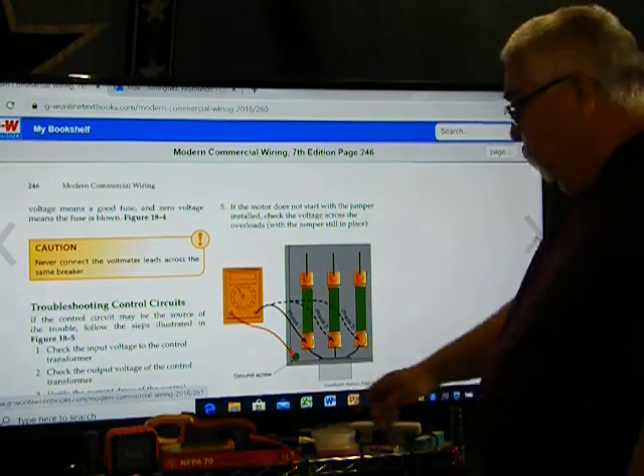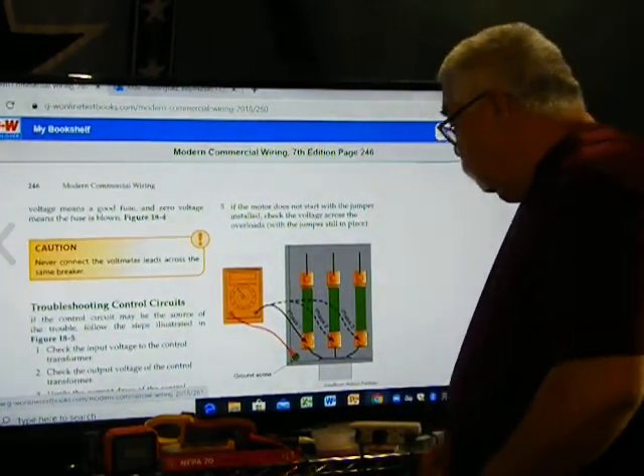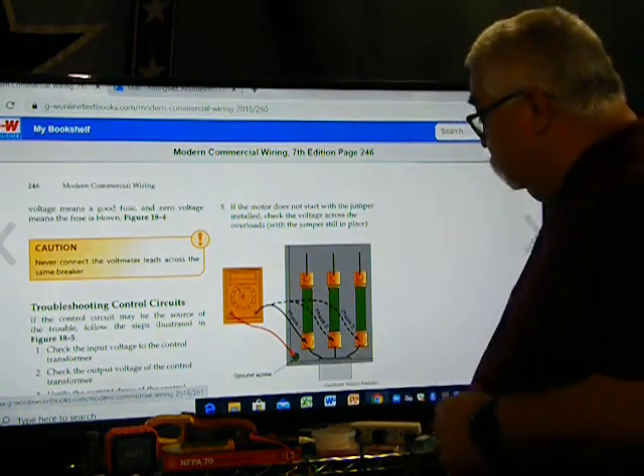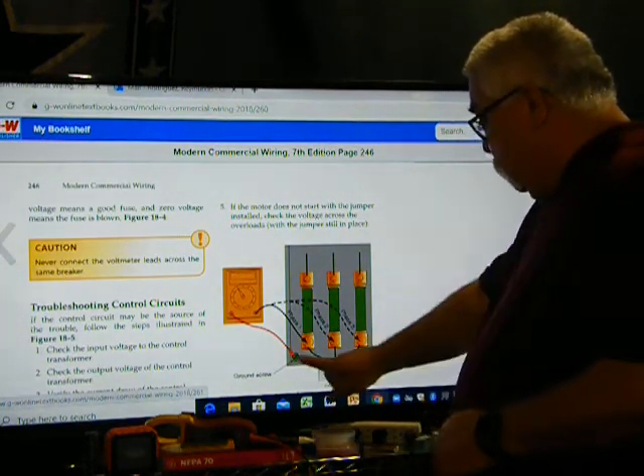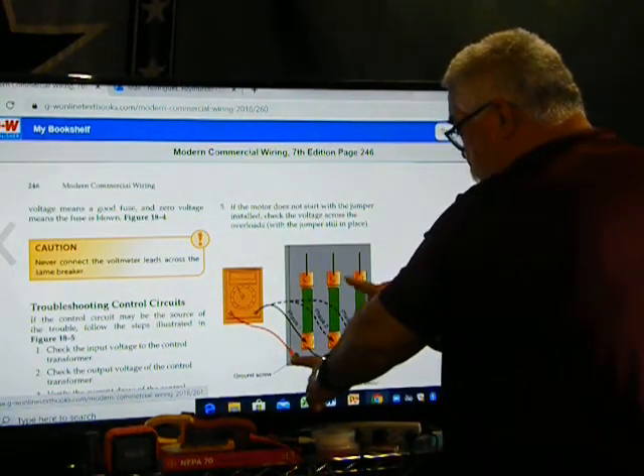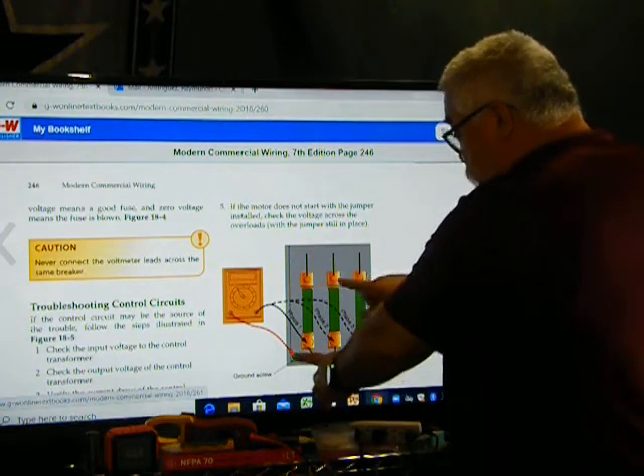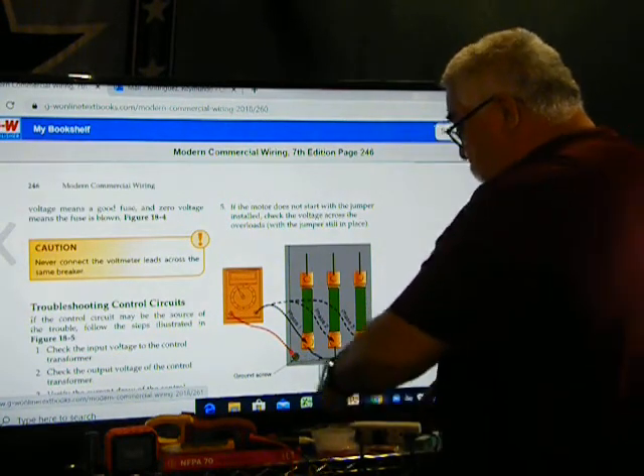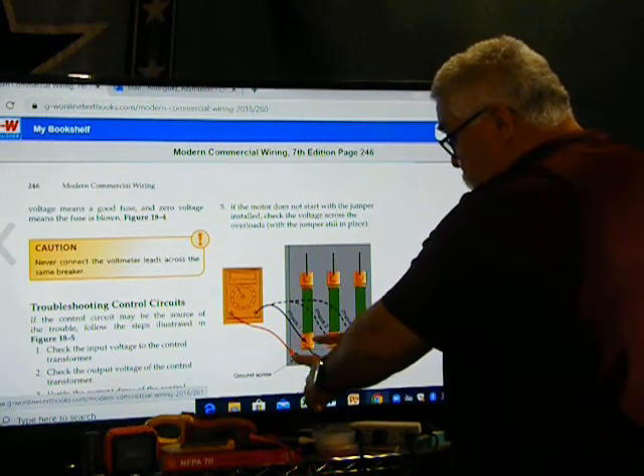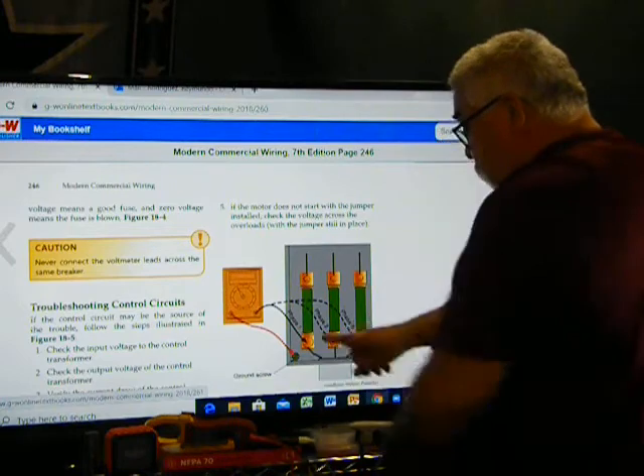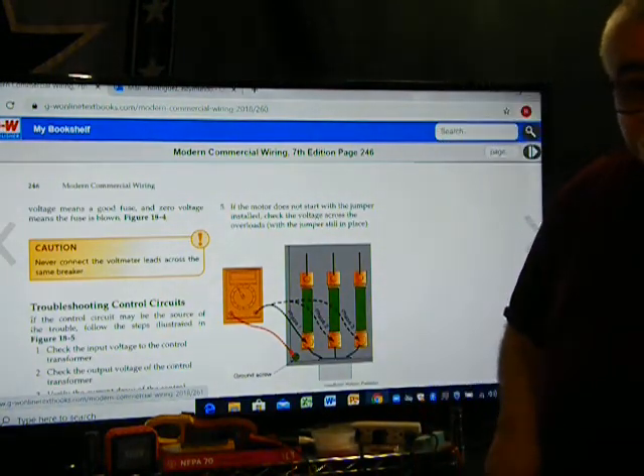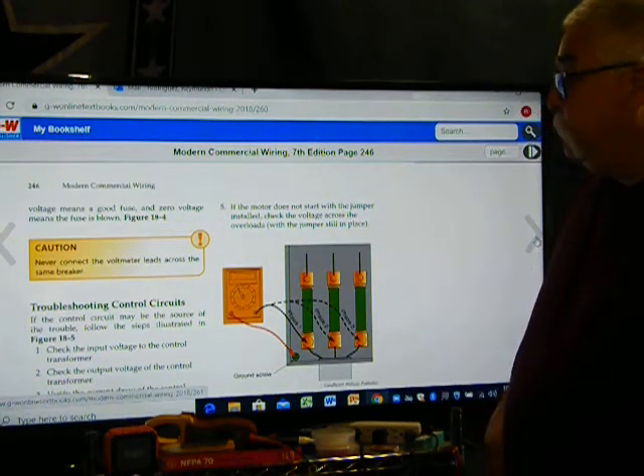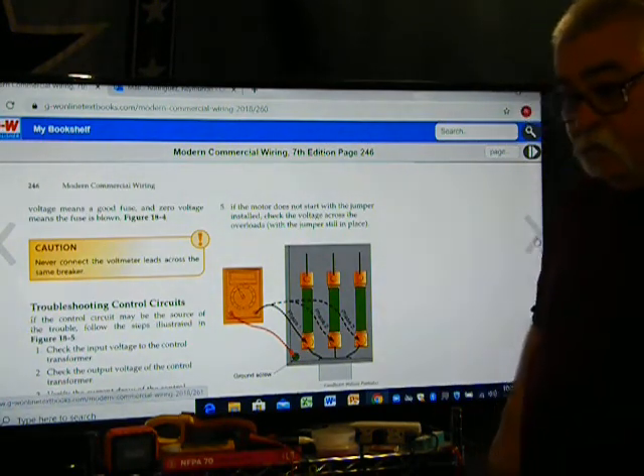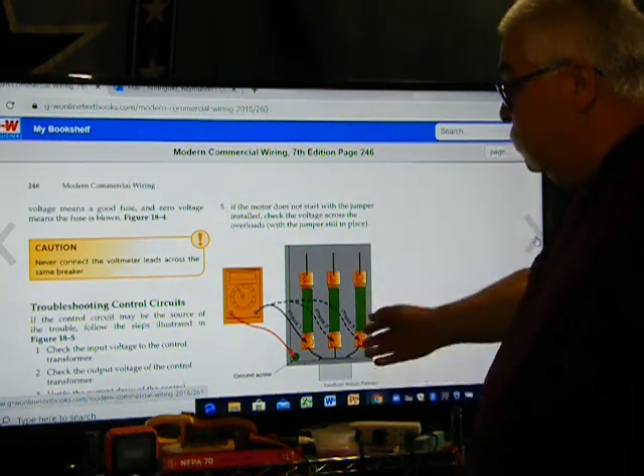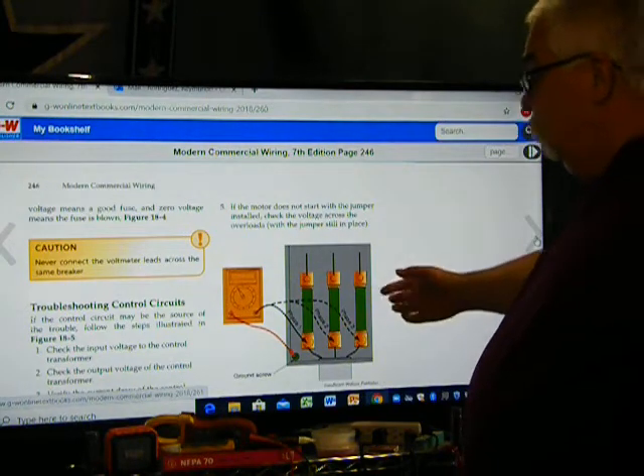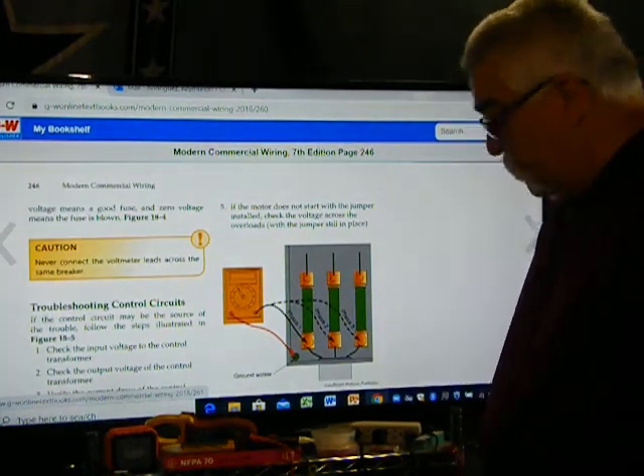Whatever the voltage may be. Okay, let's say 120 208, it's 3-phase Y. So we don't have to worry about that high leg on the B and get anybody confused there. So I go from here to hot, to hot, to hot. I got 120 volts on all three. 120, 120, 120. Okay, then I come back and I go from hot to here, and I got 0, 120, 120. That means that my fuse on A is bad. Okay, this is a textbook. Luckily I got it online. The company was real good to me. So this is how we're troubleshooting. How you can troubleshoot a disconnect.